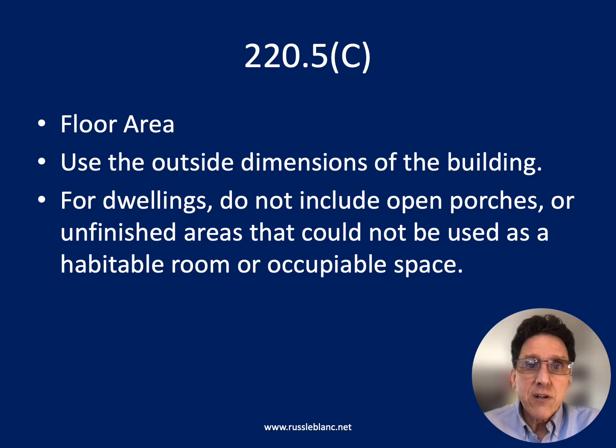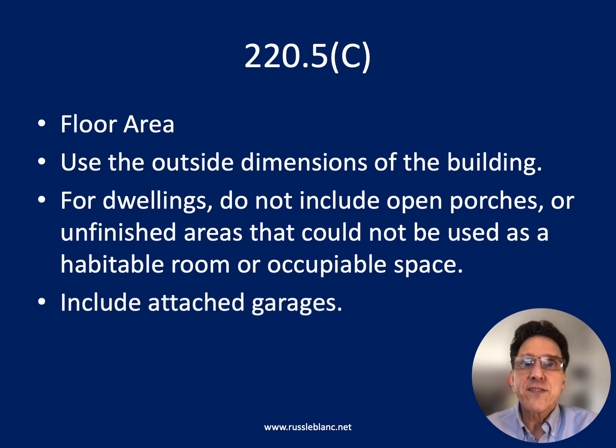Now, as far as garages go, prior to 2023, they were specifically excluded from the floor area calculation, but the references to garages got removed for 2023, so I guess we should include garages now. And that makes sense to me if you think about it. There is lighting there, and there are receptacles there, so we should include the square footage of the garage with the rest of the dwelling unit, if it's an attached garage.